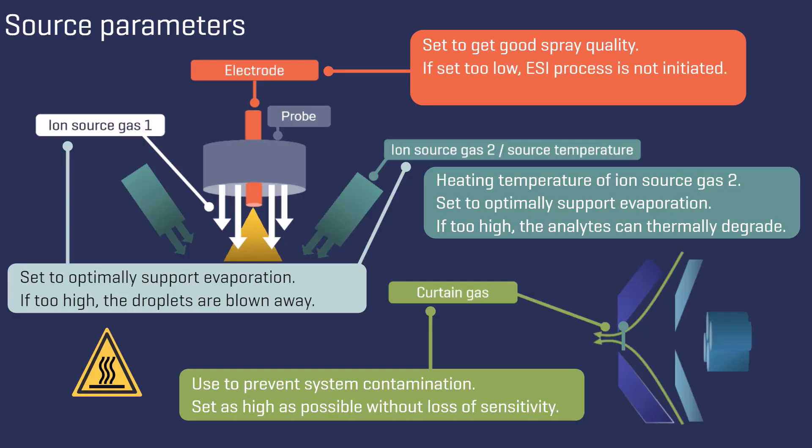If set too low, the electrospray process is not initiated. If set too high, you can observe corona discharge, resulting in poor spray quality and damage of the electrode.